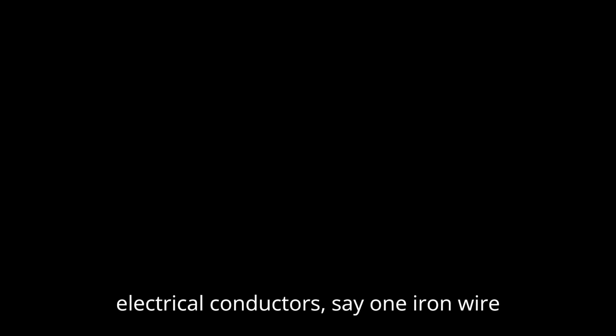They operate based on the Seebeck effect, discovered back in the 1820s. Seebeck effect. Okay. This is a fundamental thermoelectric phenomenon. It states that if you take 2 wires made of different dissimilar electrical conductors, say, one iron wire and one constantan, a copper-nickel alloy wire, and join them together at one end. Yeah, make a junction. Right. And then create a temperature difference between that measurement junction, the hot junction, which you put in the process, and the other end of the wires, the cold or reference junction. A small electrical voltage will be generated across the open ends of the wires. A voltage appears just because of the temperature difference across 2 different metals.